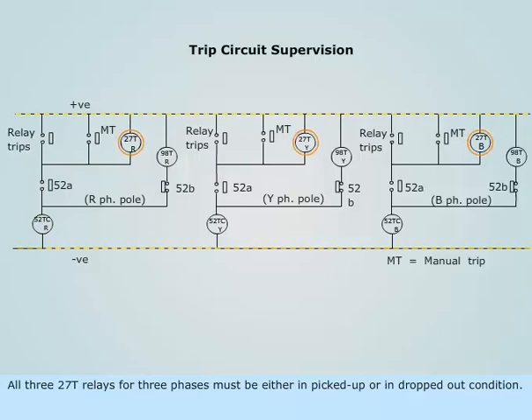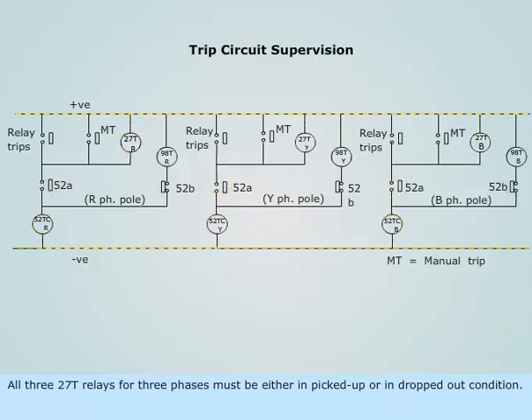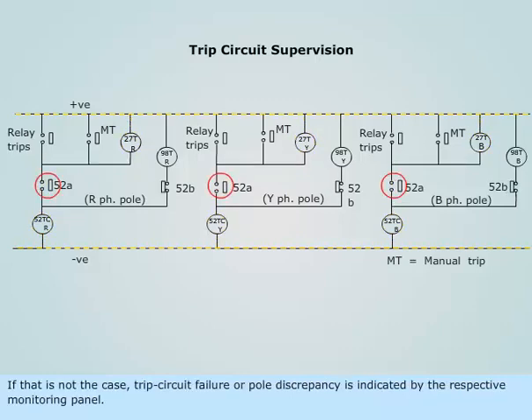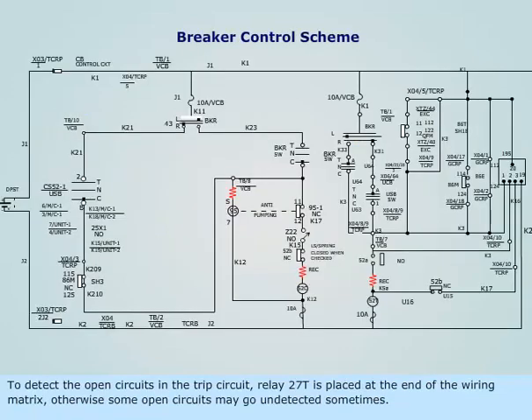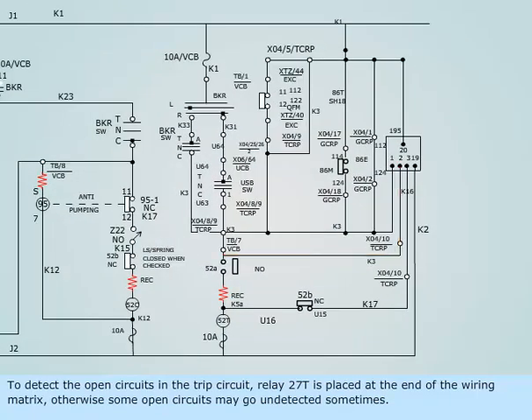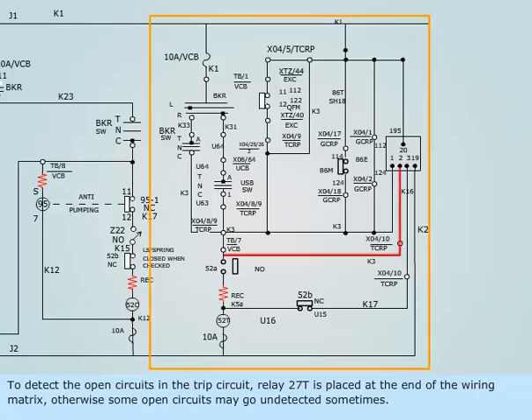All three 27T relays for the three phases must be either in picked-up or in dropped-out condition. If that is not the case, a trip circuit failure or pole discrepancy is indicated by the respective monitoring panel. To detect open circuits in the trip circuit, relay 27T is placed at the end of the wiring matrix; otherwise, some open circuits may go undetected.